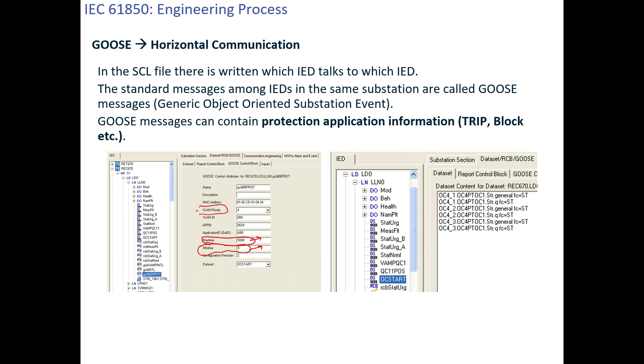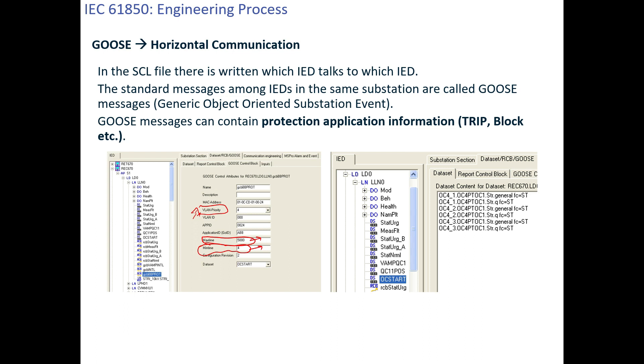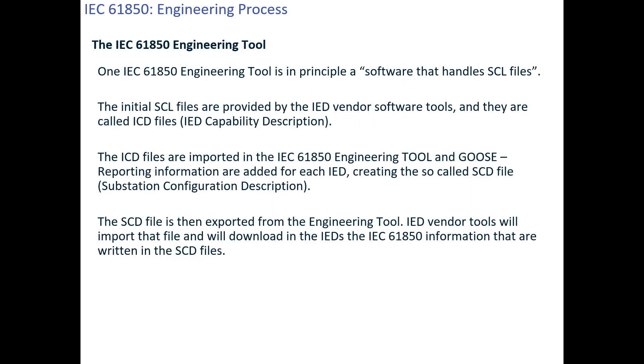GOOSE is horizontal communication. In GOOSE you create GOOSE control blocks. The important properties of a GOOSE control block include: maximum time — when there is no change in signal status, the IED keeps repeating the signal every 5 seconds; minimum time — for example 4 milliseconds — whenever there is a status change it repeats the signal. VLAN priority is the virtual LAN priority, which must be highest for GOOSE signals. The application ID must be unique for each GOOSE control block.